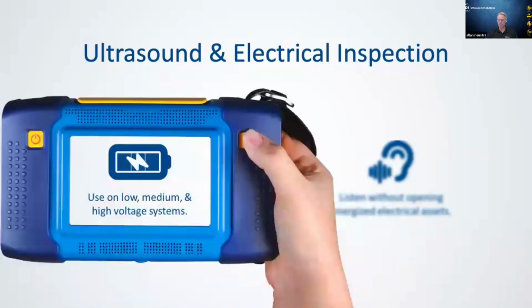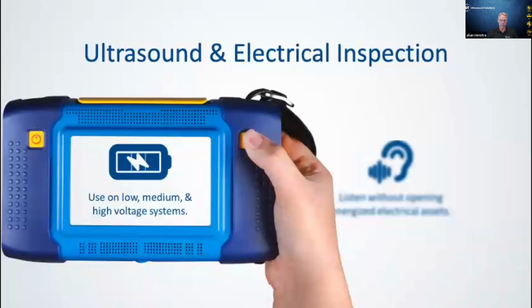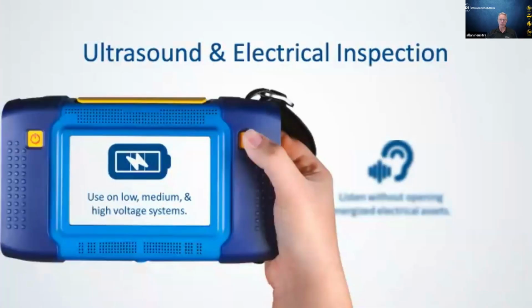Now, to focus in specifically on electrical inspections, because that last little bit was a more broad spectrum of applications, but to look specifically at ultrasound and electrical inspections, well, we can use ultrasound to detect low, medium, and high voltage systems, whether it be low-level nuisance corona, high-level destructive corona, tracking, arcing. All of these things are pointing towards an eventual asset failure, and ultrasound helps us discover not only that they exist, but where they're coming from.